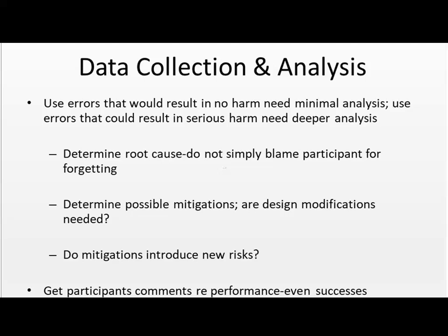Do not blame the participant for forgetting. You should determine the possible mitigations to these problems. Do we need design modifications? If you do propose mitigations, do these mitigations introduce new risks? Have you created a new risk by your solution to one risk?